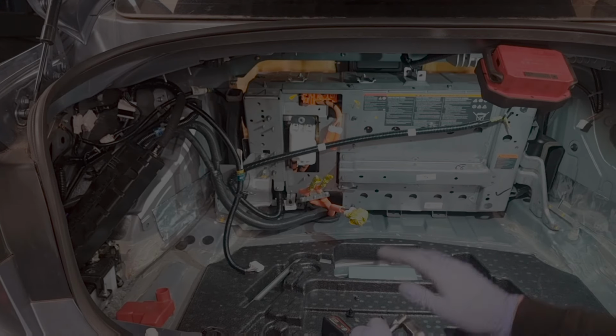So this should be around 0.7 mega ohms. We're going to do a check on this. First, check the meter, check that it goes down to 0.1, that's acceptable, and this meter is on auto. So when I put this on, right, so we said about 0.7 mega ohms, that's gone down to ohms, about 146. So that is far too low. The new one is about, I think, 700,000. So 700,000 down to 146 — that is way too low.